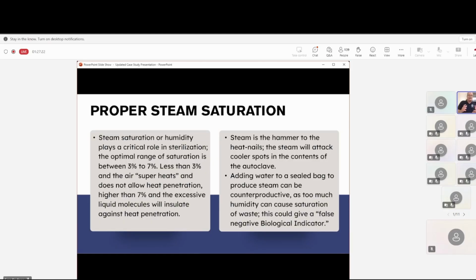And anybody that has something dry, even if you put it in a pressure cooker and it's dry, it's going to take forever to get it to penetrate and get in. You might as well just stick it in your regular oven at home. If it's greater than 7%, now we're getting too much humidity. Those in healthcare understand this, because once you start getting more than 7, 8, 9, 10%, the humidity gets on their packs and it will seal it and keep the heat from going in and getting the sterilization that they need on all their operating equipment, utensils, and other things. So you can have too little or too much.